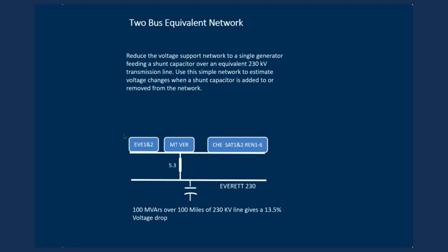So once we have that voltage support network, we can apply some reduction techniques through series and parallel path combinations to reduce that network to where we have all the generators working in parallel through a single equivalent line to the capacitor. And then we can figure out the voltage drop on this bus if we remove the capacitor using the TLAR rule that 100 megavars over 100 miles of 230 kV gives a 13.5% voltage drop.